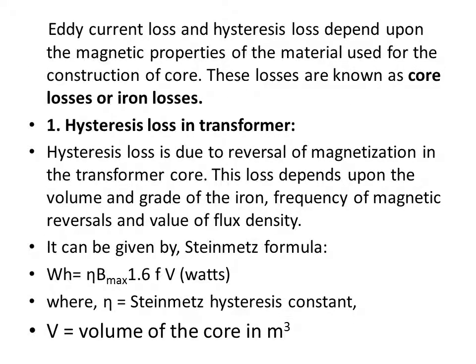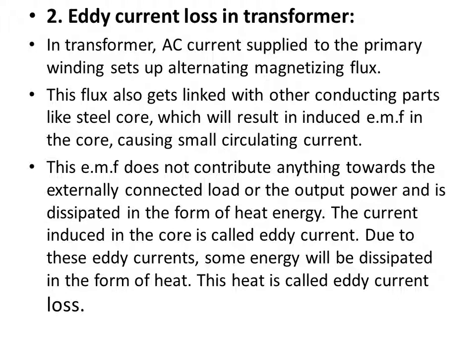Hysteresis loss is due to the reversal of magnetization in the transformer core. This loss depends upon the volume and grade of iron, frequency of magnetic reversal, and the value of flux density. The equation is: Wh = Kh Bmax^1.6 × f × V, where f is the frequency of magnetic reversal, V is the volume of the core, and Bmax is the maximum flux density.